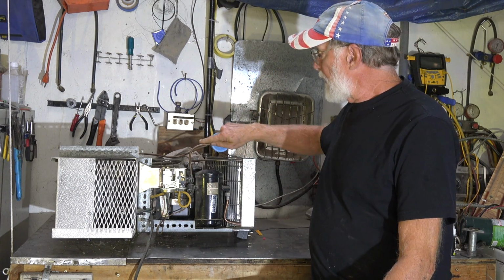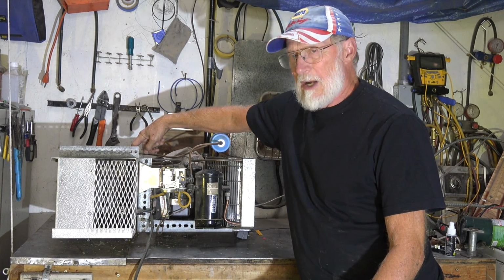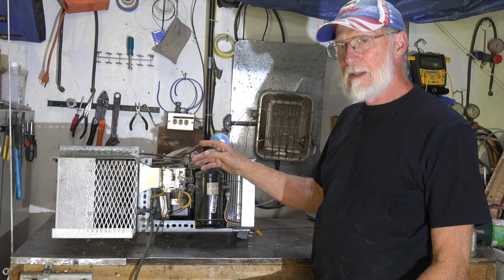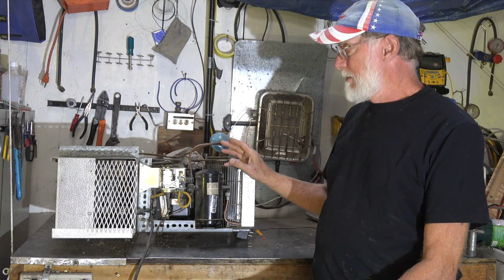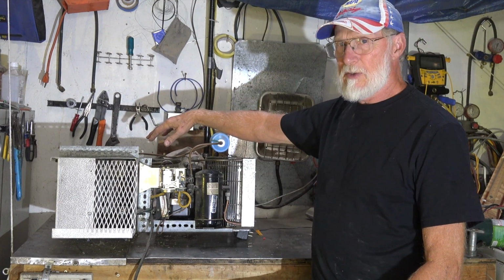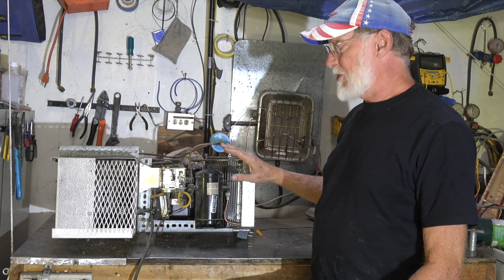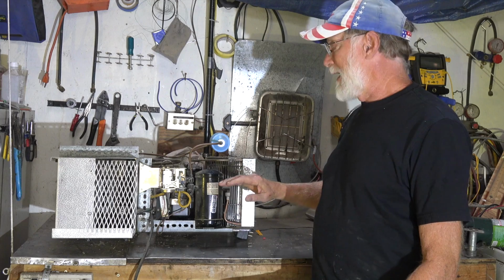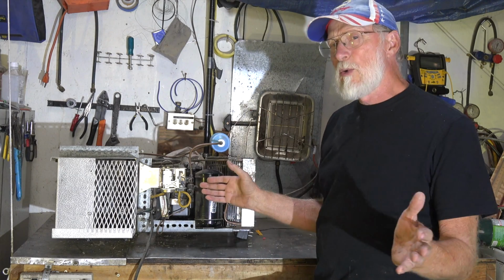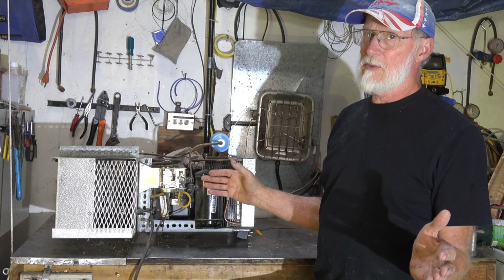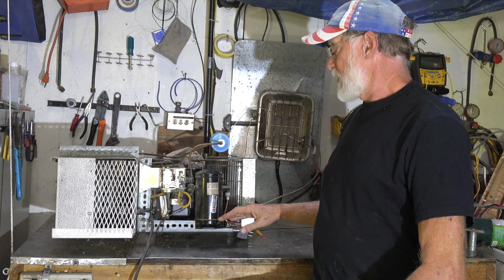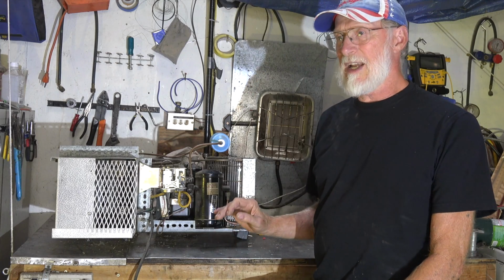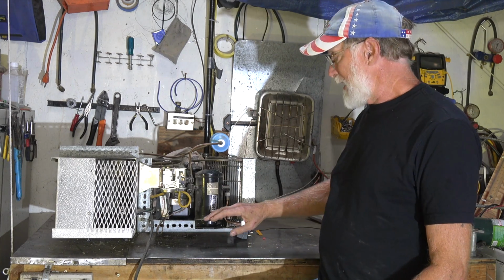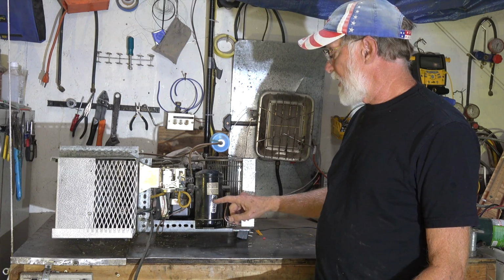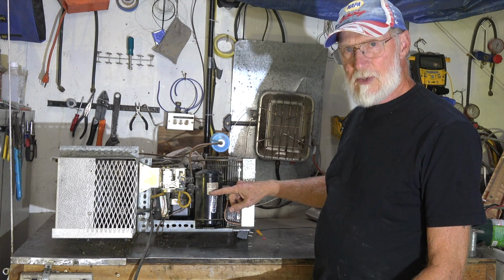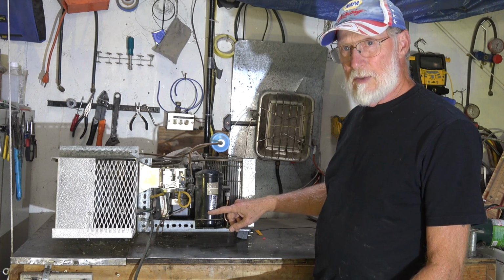So you've got liquid refrigerant coming in here, with the TXV down here by the evap. It's going to open up because it wants to maintain the superheat, so it's going to dump a bunch of refrigerant in there. It's going to need a lot more refrigerant than it would if it was just holding temperature. There's quite a bit of difference between those two loads, so you need some place for this extra refrigerant to go. That's why the receiver's here. This thing is going to start filling up when the load drops off, and it'll drop down when the load increases.